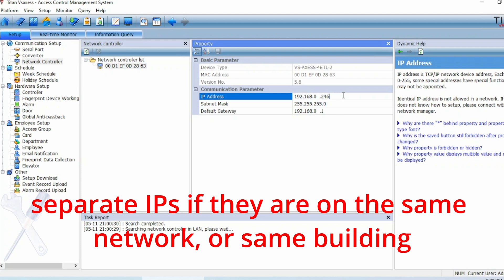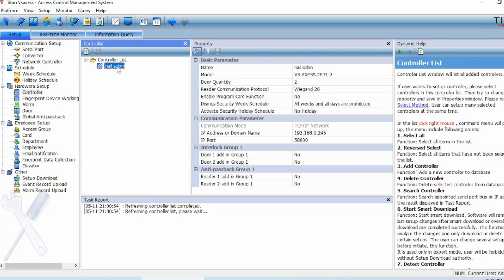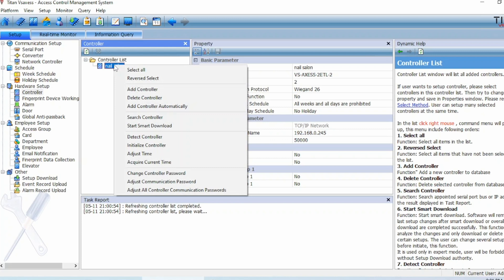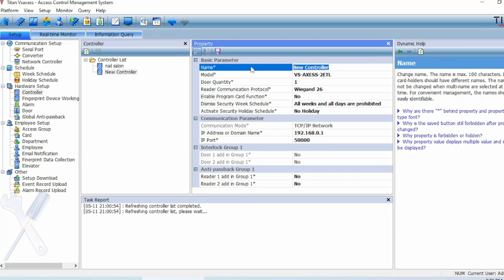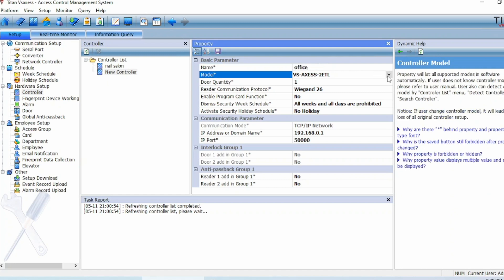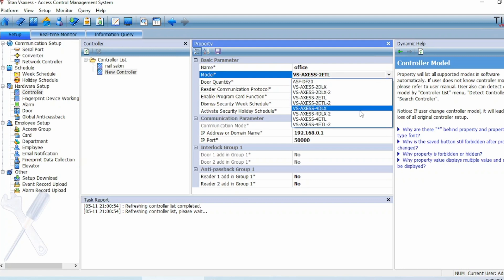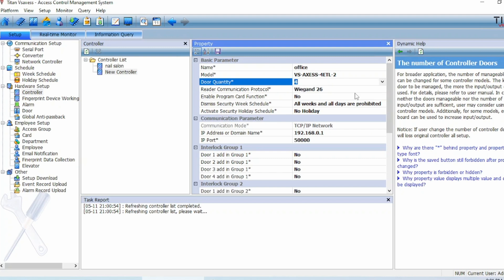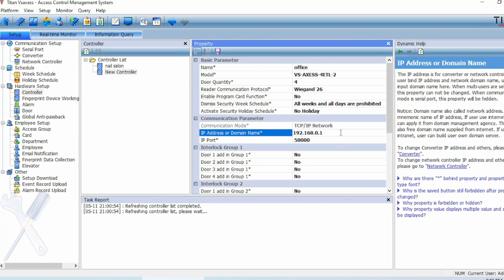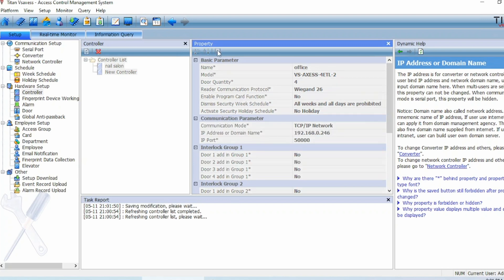If you don't assign separate IPs, the Titan software will get confused. Now that we've got the 246 IP address, go ahead and click on Controller on the left-hand side, right-click on it, and then go to Add Controller. Give it a name — here we're going to give it the name of the office building. Don't forget to change the model number; the model number is the four-door version, ETL version 2. There are a total of three doors but there's no such option, so choose the four-door. Be sure to specify the IP address, which is 246, then click Save.